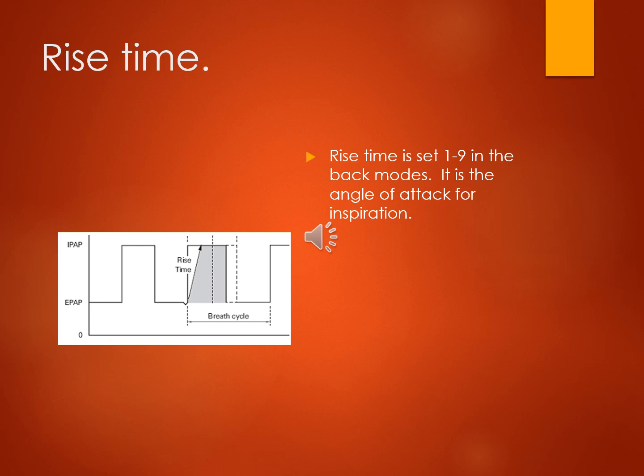That's something we really need to pay close attention to, because if we're setting a patient up, say for transport, we're going to set the patient up on the same settings that they're receiving at the sending facility. We put the pressure control the same, the PEEP the same, and the rise time is different. Say somebody was screwing around on the ventilator before, doing some training, and left it on 9. Now I think I should be getting very similar volumes, and I put the patient on there and they're not meeting the volume. Well, that's probably the rise time.